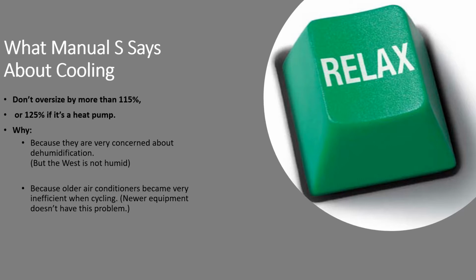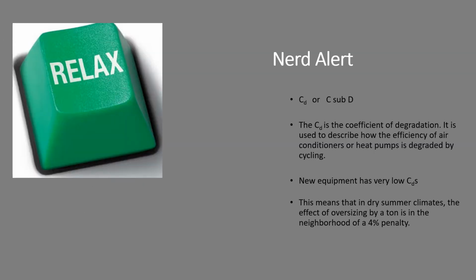Of course you can oversize air conditioners, but the reason they're so worried about that is dehumidification. And when we are at 95 degrees, chances are that air conditioner is running a long time. It's not very humid outside, and as that air conditioner runs, it even dries the indoor air out more and more. So there's the nerdiest slide of today's presentation. It's called the C sub D, or coefficient of degradation. Newer heat pumps have a much lower coefficient of degradation. That is the penalty you pay for short cycling. Newer systems, the penalty for short cycling, at least from an energy perspective, is not all that high.